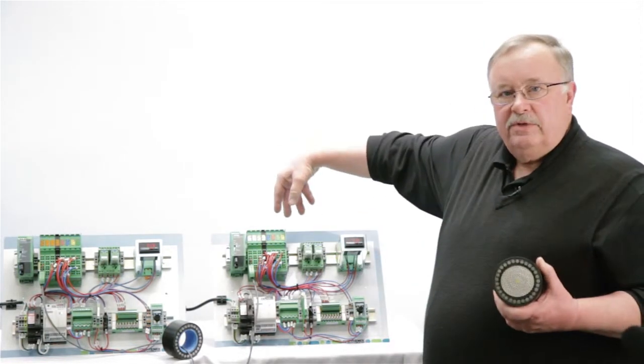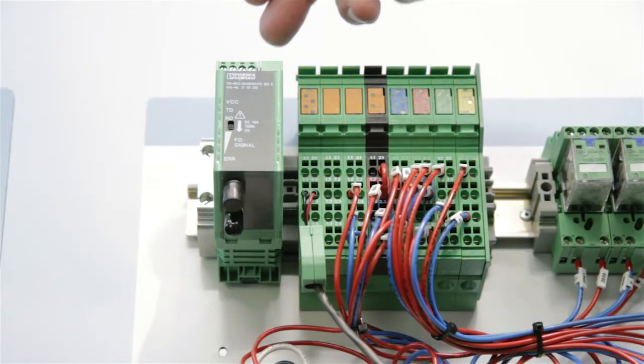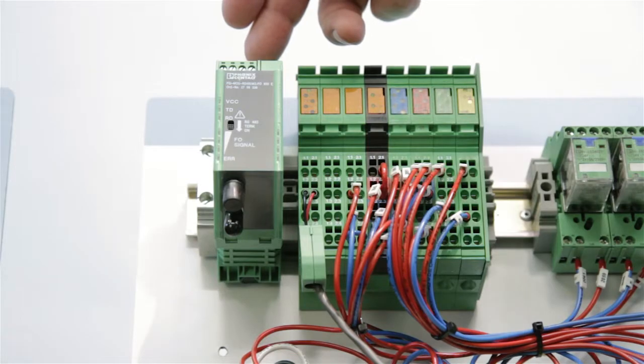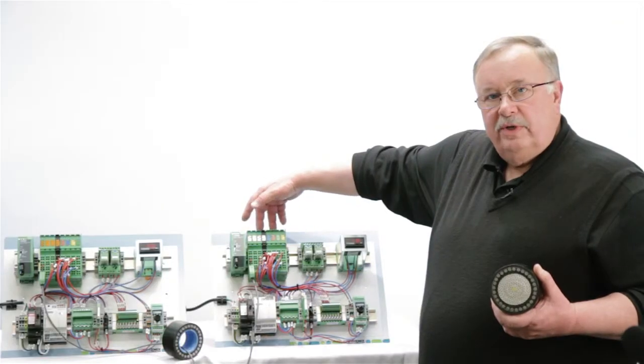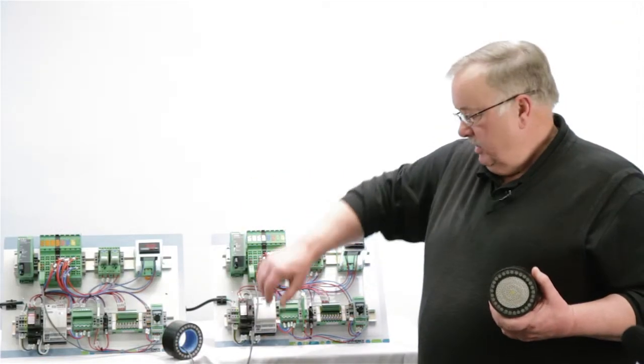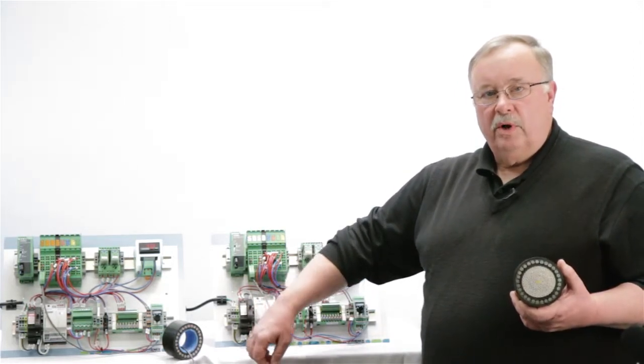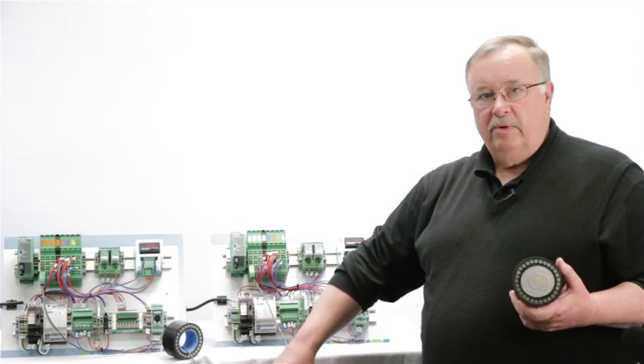What it does is, in the case of the multiplexer, the wires are wired into the wiring harness on each one of the wiring caps on the multiplexer, and then are transitioned to an Interbus protocol and sent over protocol through a cable, either shielded twisted pair of copper or it could be even fiber optic.